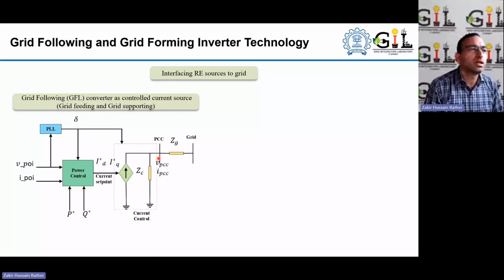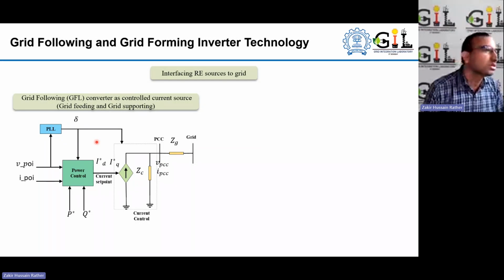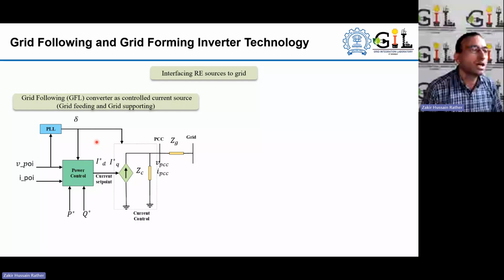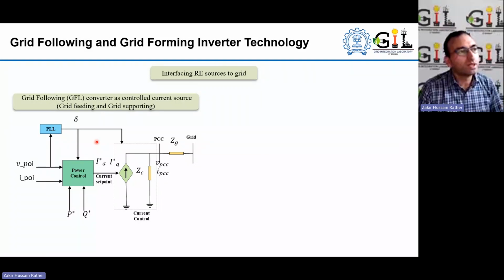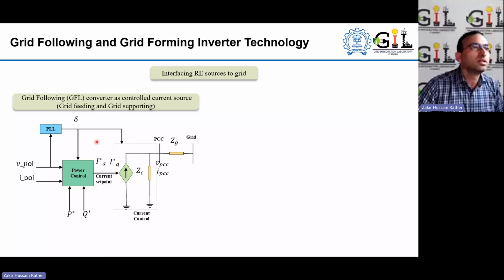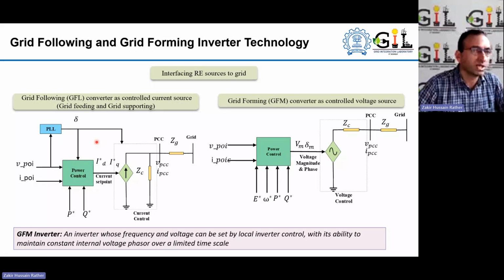And most of the small scale renewable plants in the grids across the world, and in India also, are of grid feeding technology. For example, rooftop PV and other smaller capacity RE generations are of grid feeding technology. As for grid supporting technology of the grid following, it includes additional grid support services, which include reactive power support, frequency support, and in some cases inertial support, and other ride-through capabilities. So this is, in simple terms, the grid following, IBR converter technology, that is predominant in the utility scale or otherwise plants in RE plants in the system.